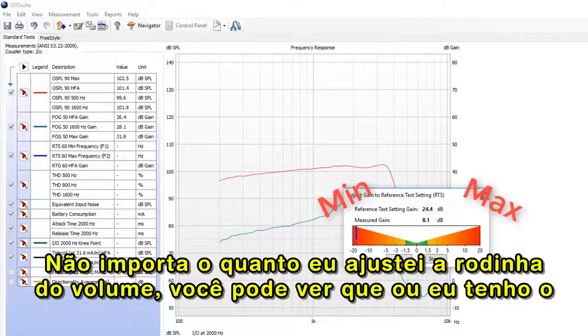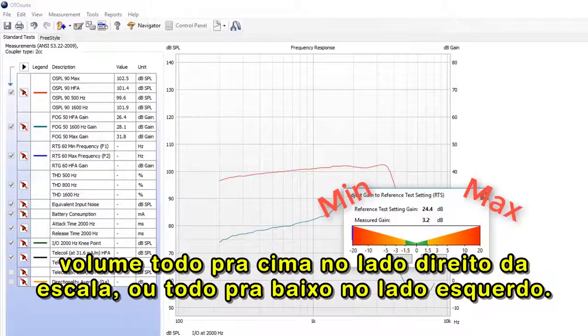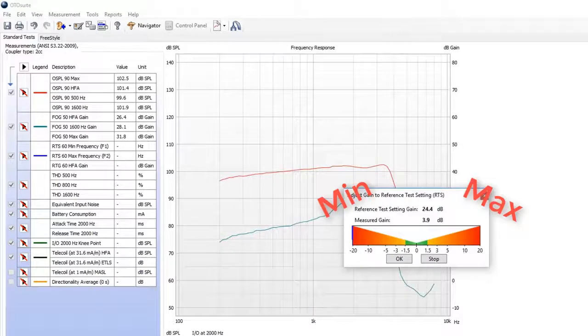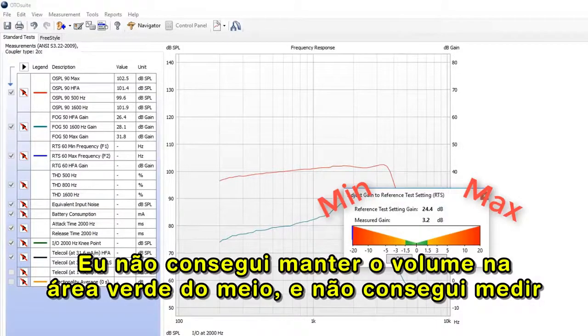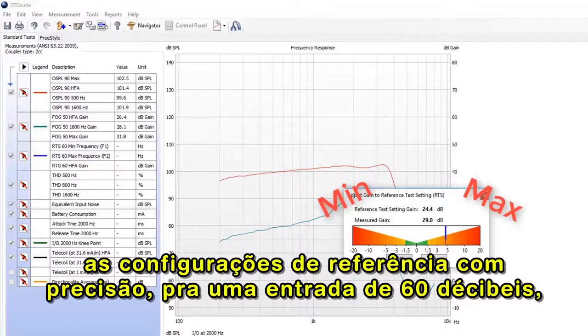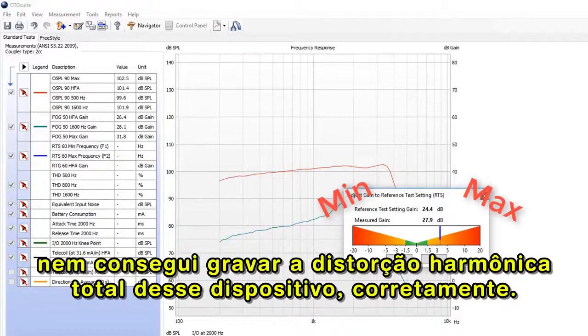volume. No matter how much I adjusted the volume wheel, you can see that I either have the volume all the way up on the right-hand side of the scale or all the way down on the left-hand side of the scale. Since I couldn't get it in the middle green area, I was not able to accurately measure the reference test settings for a 60 decibel input, nor was I able to accurately record the total harmonic distortion of this device.